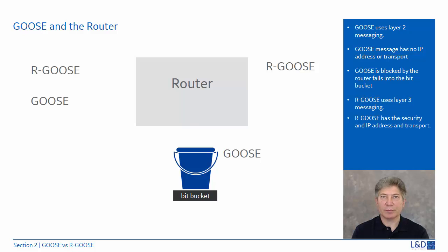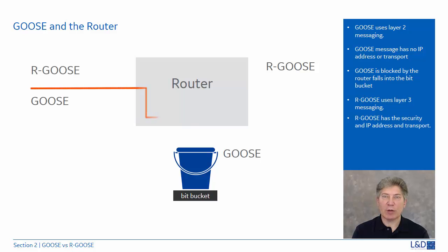Let's take a look at what happens to a standard GOOSE and a Routable GOOSE when they reach a firewall on a router. The standard GOOSE is a multicast Layer 2 messaging service originally intended for use only within a LAN environment. GOOSE messages don't have an IP address or transport capabilities — when it reaches a router, the firewall doesn't know what to do with it and drops it into a bit bucket, essentially blocking it from getting past a router.